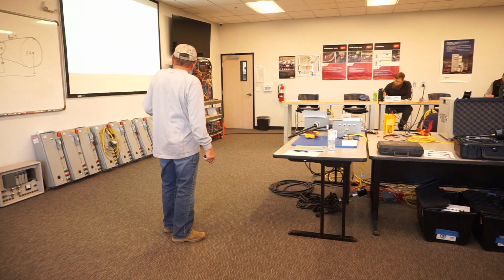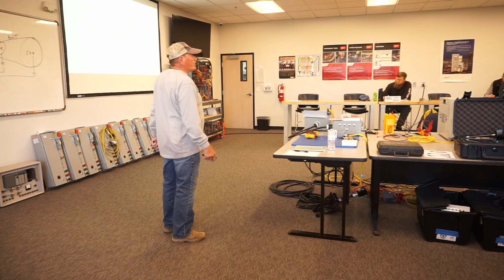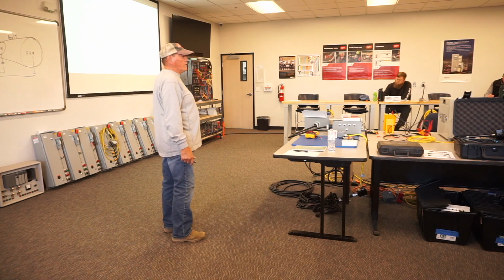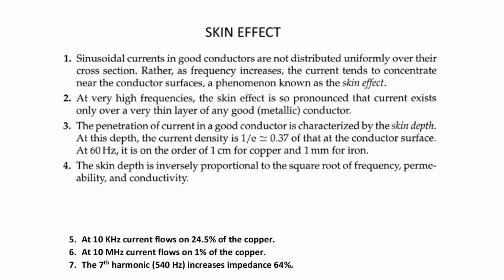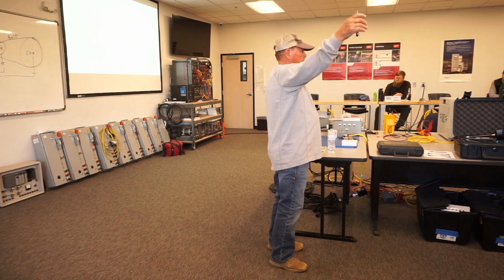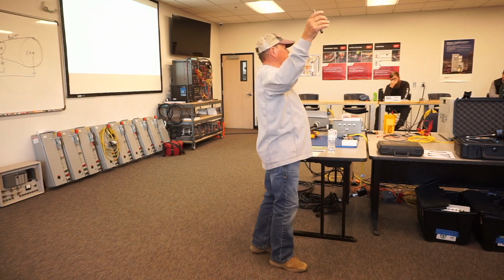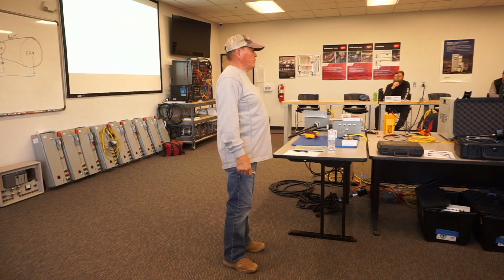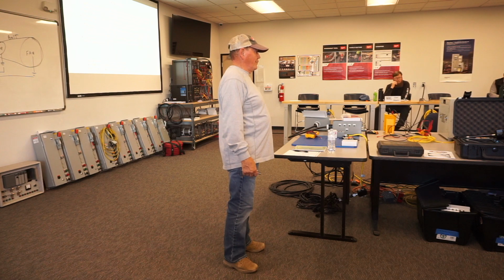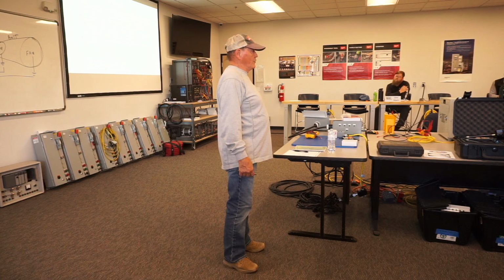So the 7th harmonic increases 64%. You've increased the impedance of that conductor 64% at the 7th harmonic. So that's why building wire does not work as a low impedance path for bleeding high speed frequencies off of drives. Because a drive is going to have a lot higher than 7th. It's going to have 15th and 21st all the way up to the 50th harmonic. What's 50 times 60? Well, you got 2 zeros there and a 30. That's 3,000 hertz. That's what's being generated by a drive, right?